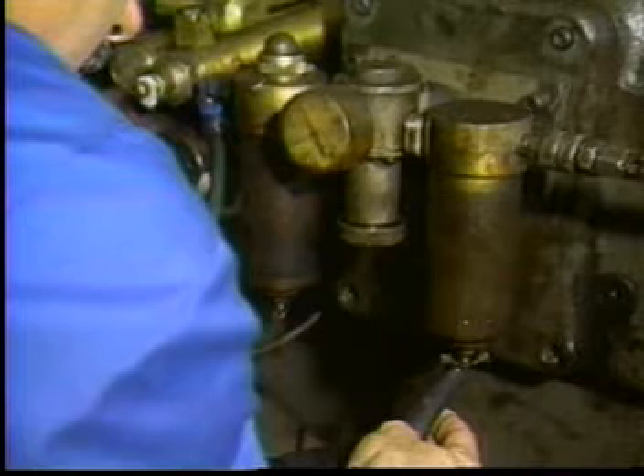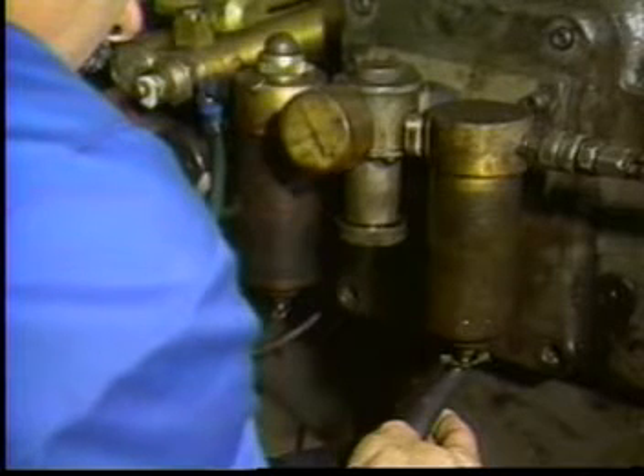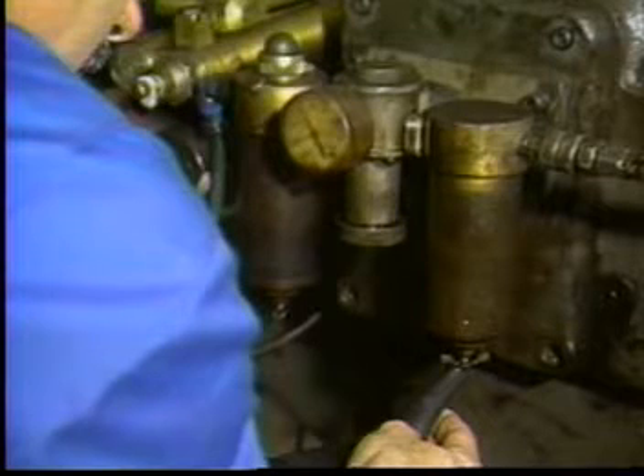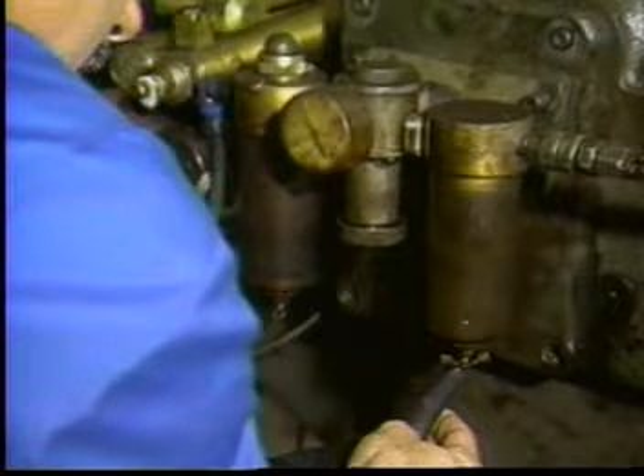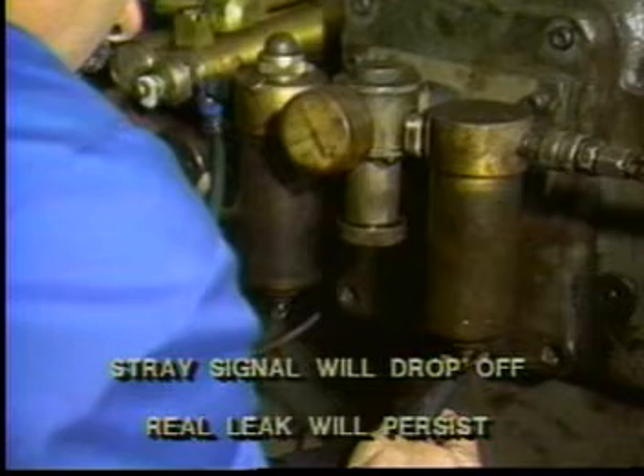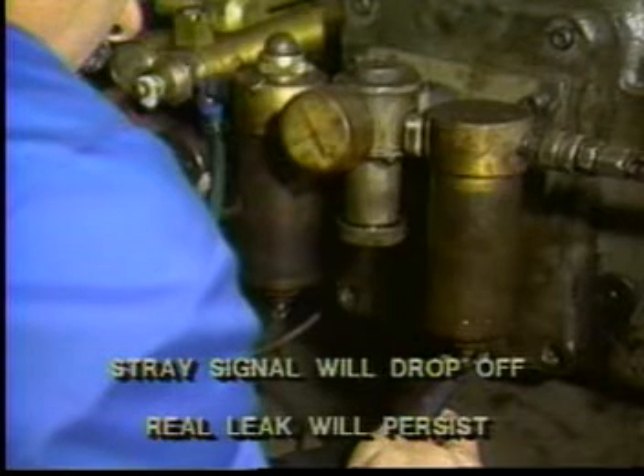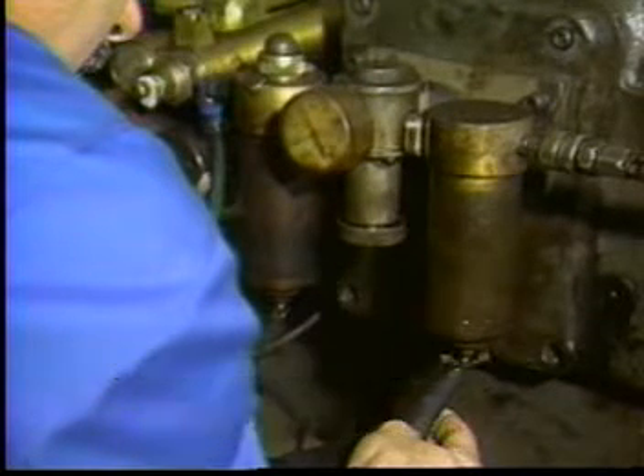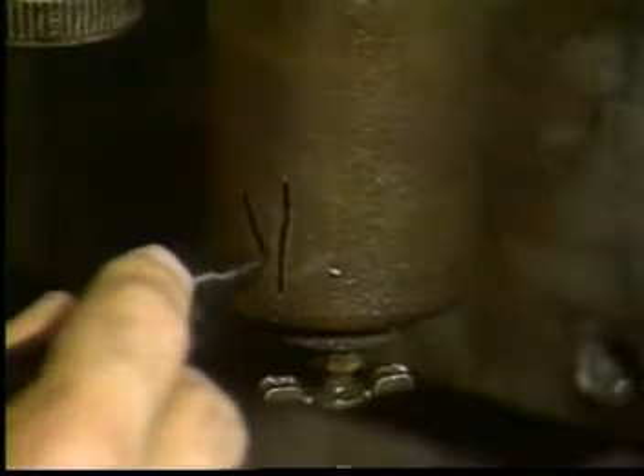In certain situations, a stray signal may be heard. To make sure you're hearing a real leak and not a stray signal, place the rubber probe directly over the leak site. A stray signal will drop off. The sound of a real leak will persist. These 5 steps are all you'll need to find most leaks.